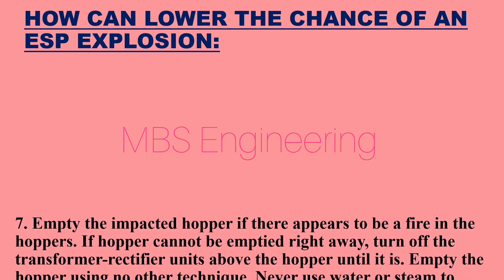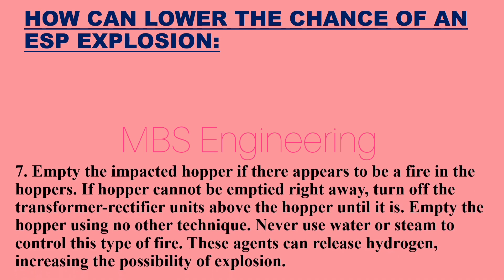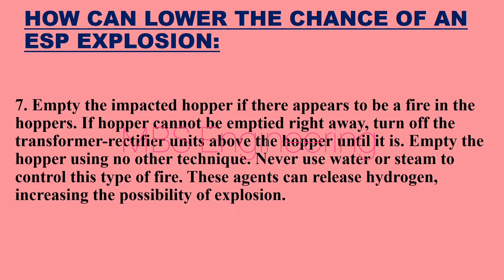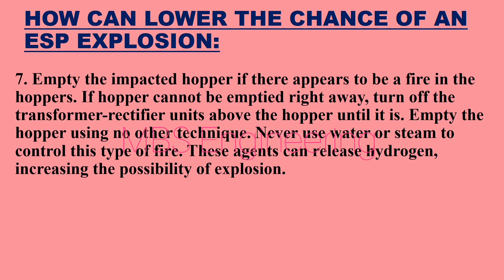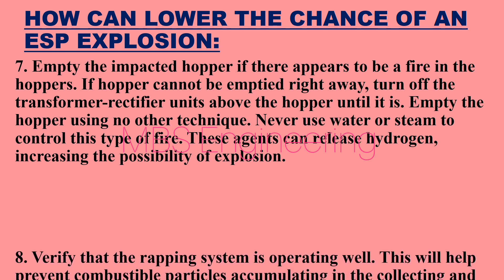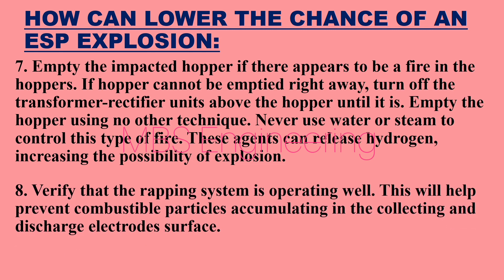Point 7: Empty the impacted hopper if there appears to be a fire in the hoppers. If the hopper cannot be emptied right away, turn off the transformer rectifier units above the hopper until it is empty. Never use any other technique — and never use water or steam to control this type of fire, as these agents can release hydrogen, increasing the possibility of explosion.